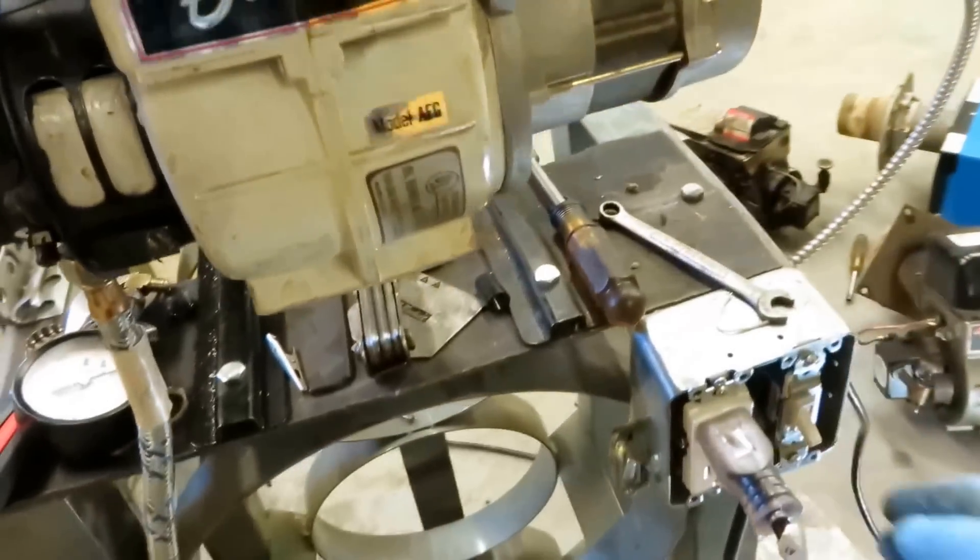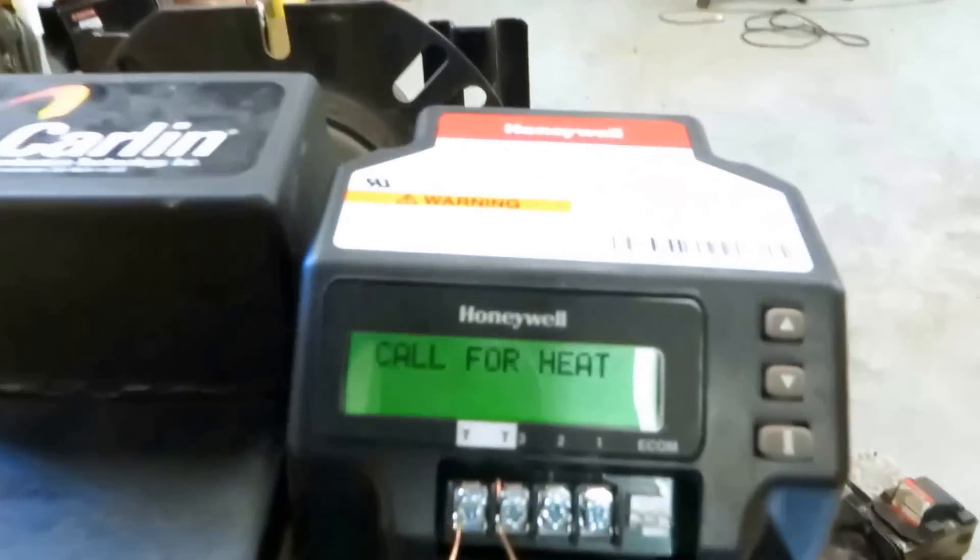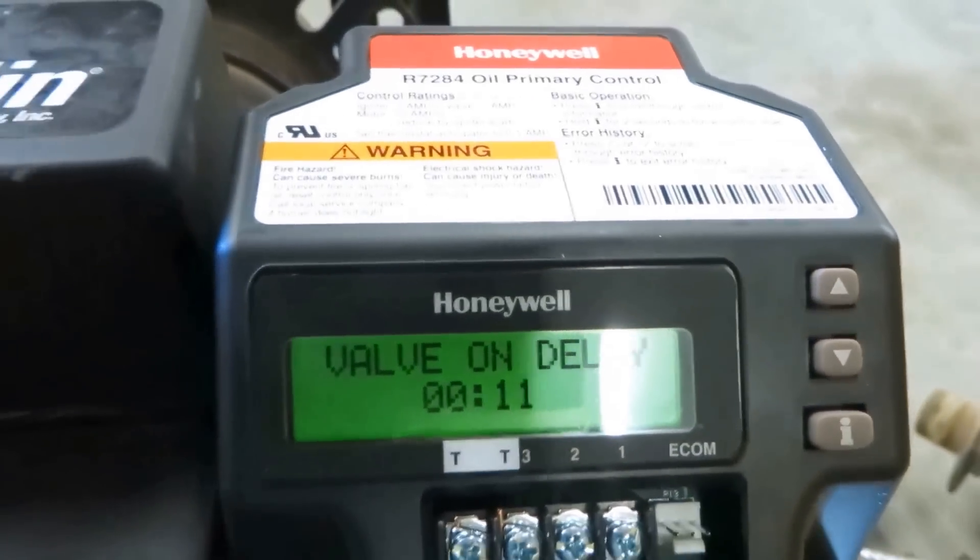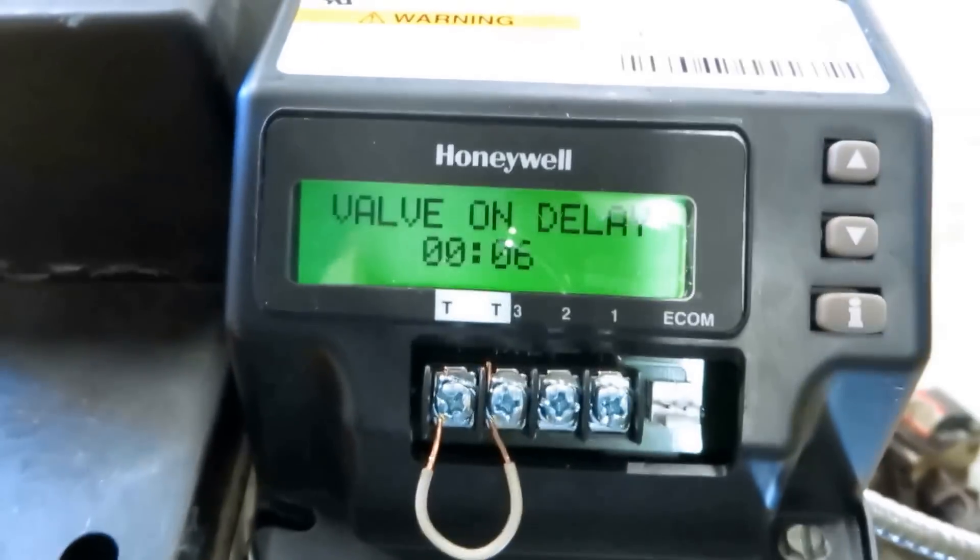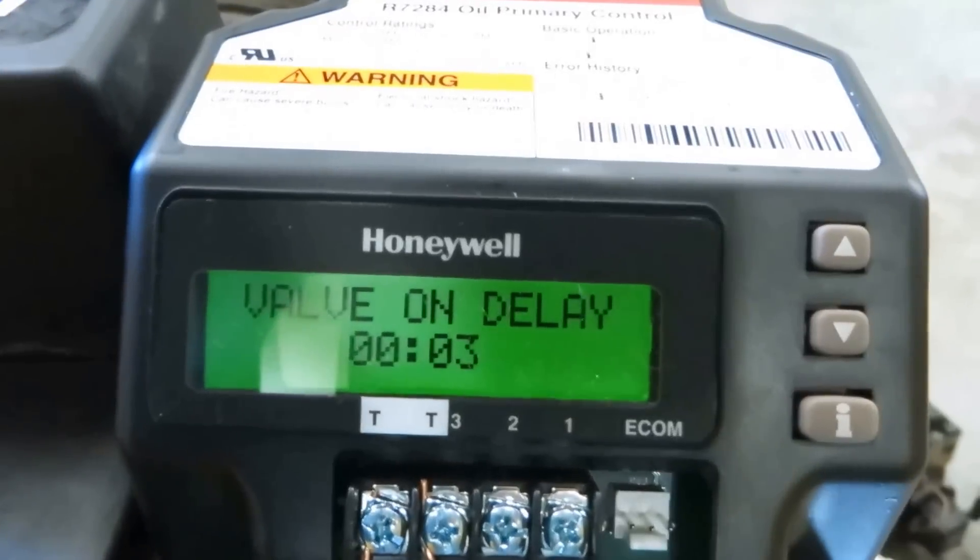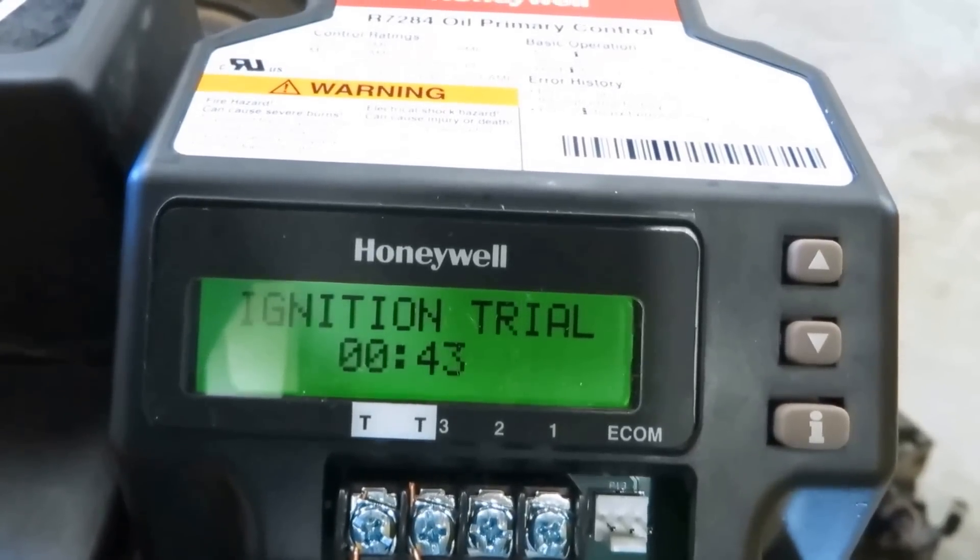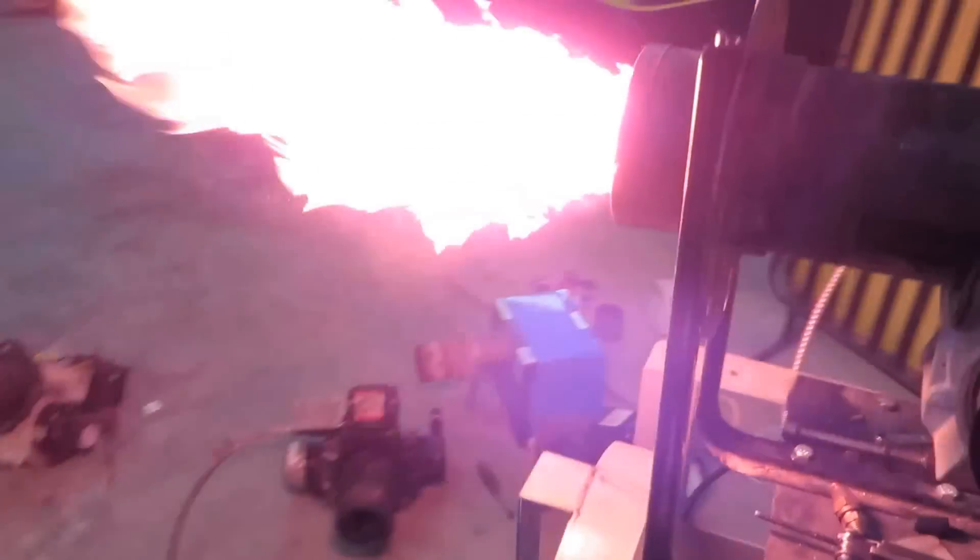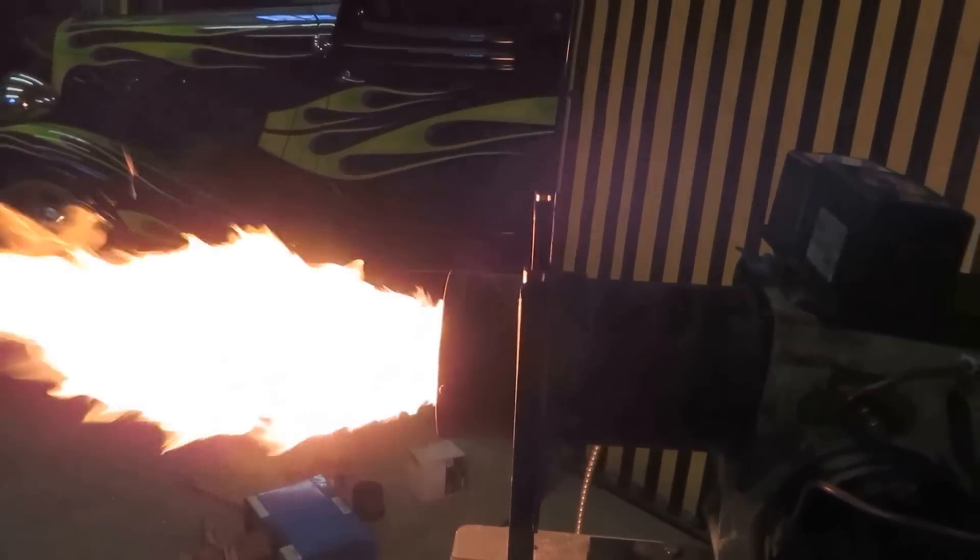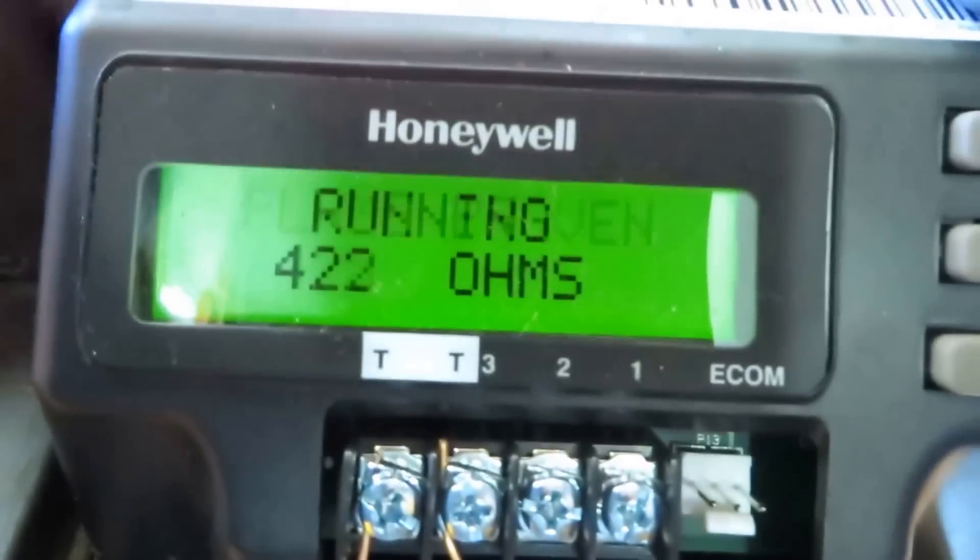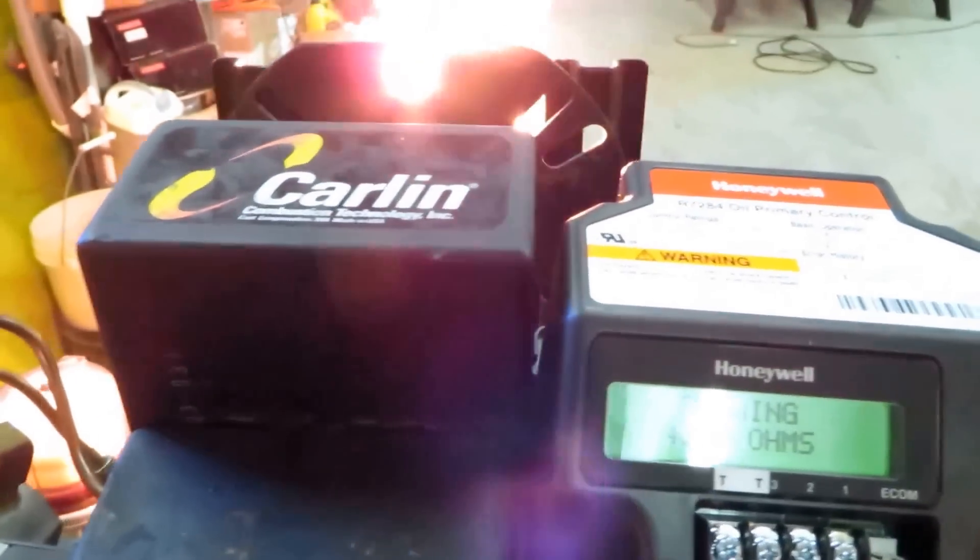Call for heat. Got our pre purge, we're coming up to speed. We're sparking. Got our delayed oil valve, going to kick in in a minute there. Pressurizing now. Firing up. Run for a bit. Transformer shuts off.